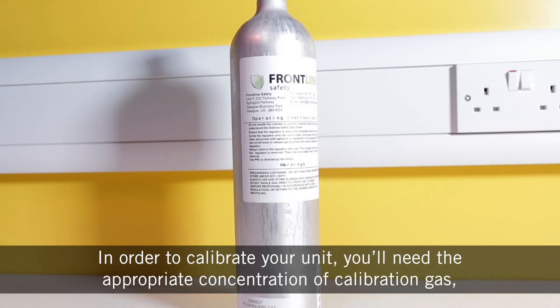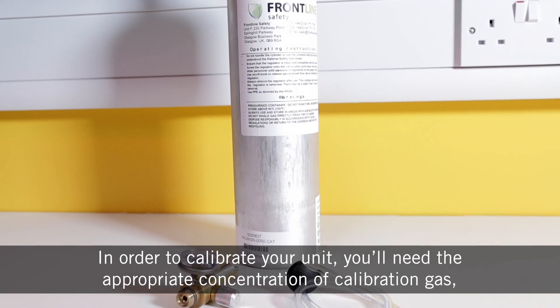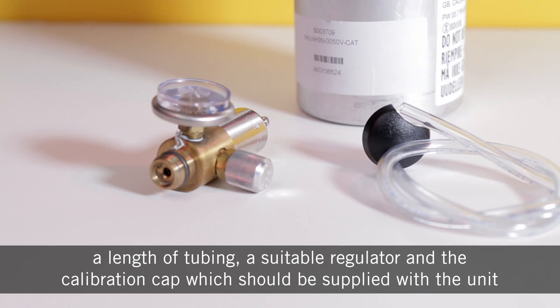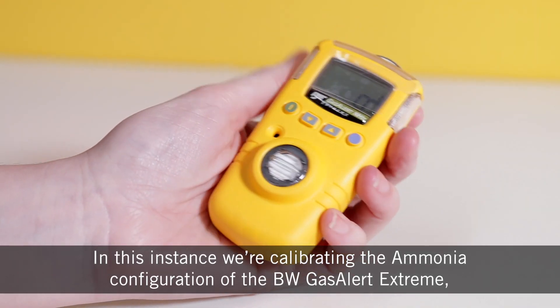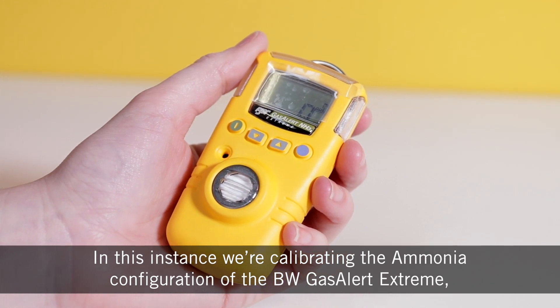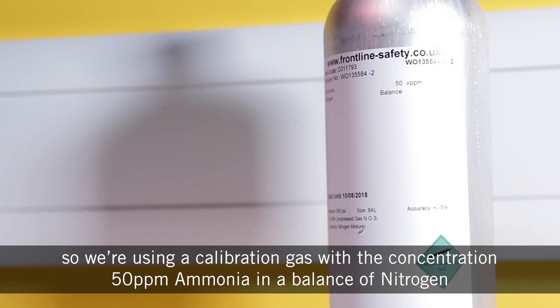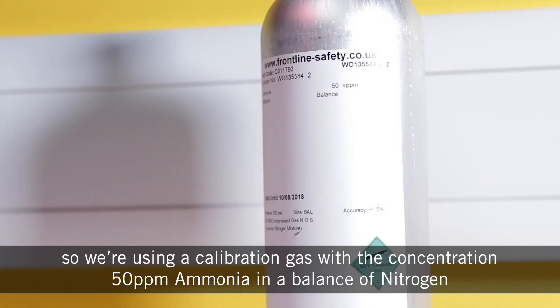In order to calibrate your unit you'll need the appropriate concentration of calibration gas, a length of tubing, a suitable regulator, and the calibration cap which should be supplied with the unit. In this instance we're calibrating the ammonia configuration of the BW GasAlert Extreme, so we're using a calibration gas with the concentration 50 ppm ammonia and a balance of nitrogen.